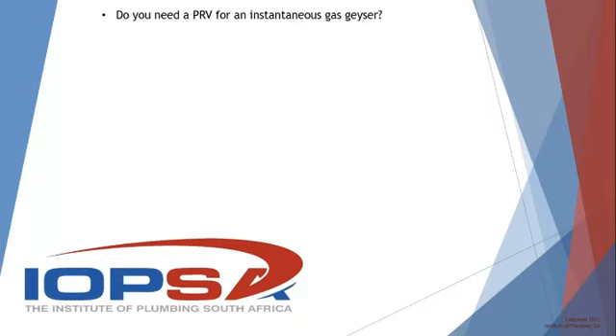But more importantly, guys, I noticed there were a couple of gas questions there. The biggest thing we need to bear in mind, especially if you're going to be signing a COC on an installation, is that 10252 part 1 says, in most cases, the instantaneous water heating process is triggered by a differential pressure switch and an orifice restrictor. This causes higher downstream hot water flow pressure drops than storage water heaters. Therefore, pipe design, pipe sizing, and simultaneous use of fittings shall be considered and calculated to ensure sufficient hot and cold water balanced at the terminal fitting.